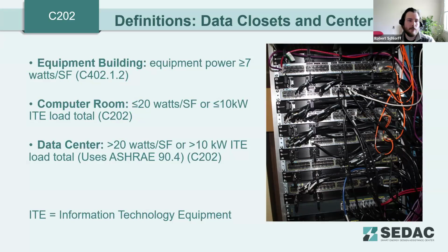And then data centers will be the step above computer rooms. Those are spaces that are greater than 20 watts per square feet or greater than 10 kilowatts of ITE load total. So the key here is to identify what type of equipment is within the space and what the load of that equipment is, and then that can help you determine the designation for that space, whether it be a computer room or a data center.